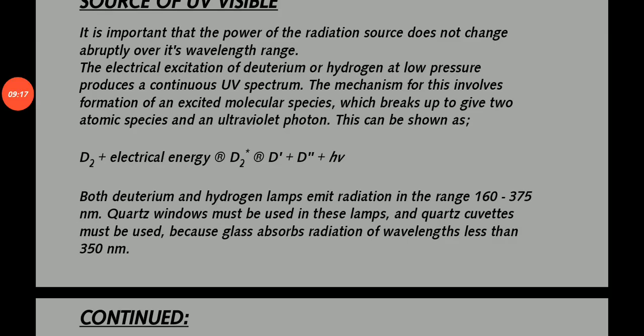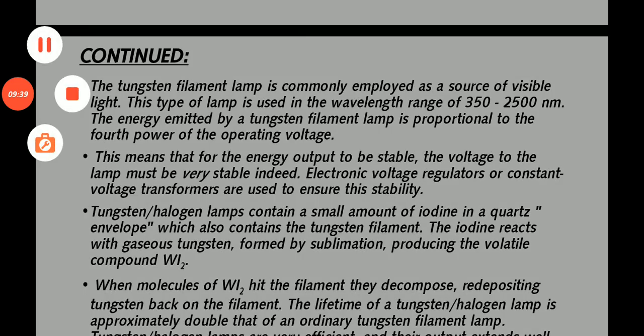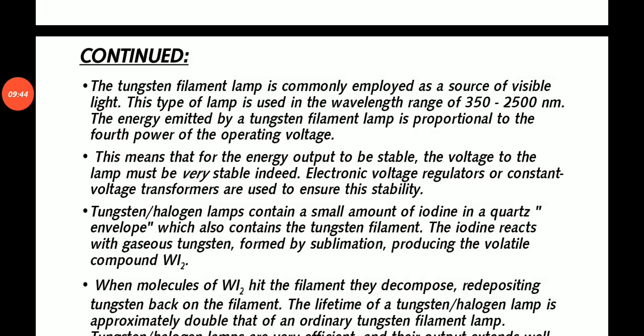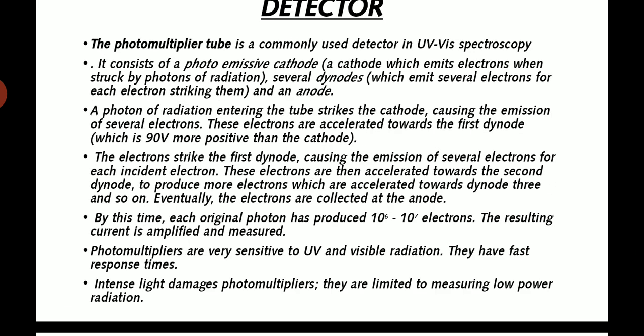Both deuterium and hydrogen lamps emit radiation in the range 160 to 375 nm. Quartz windows must be used in these lamps, and quartz cuvettes must be used because glass absorbs radiation at wavelengths less than 350 nm. A tungsten filament lamp is commonly employed as a source of visible light. This type of lamp is used in the 350 to 2500 nm range. This means that for energy output to be stable, the voltage of the lamp must be constant. Electronic voltage regulators or constant voltage transformers are used for stability. Also used are tungsten halogen lamps containing a small amount of iodine in quartz envelopes, which also contain a tungsten filament. The iodine reacts with gaseous tungsten formed by sublimation, producing volatile compounds.